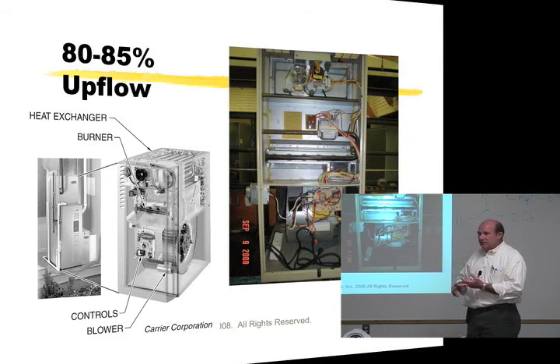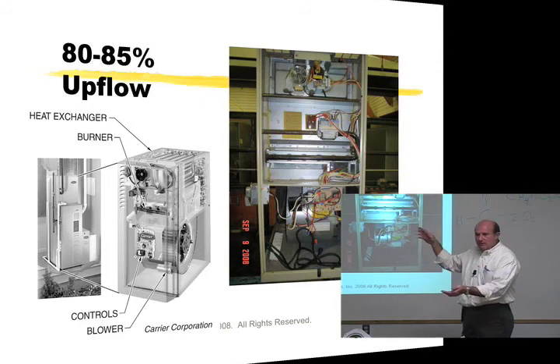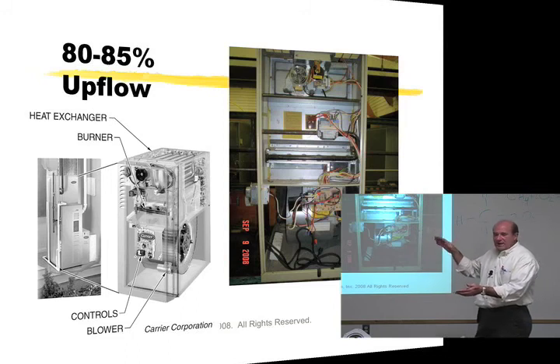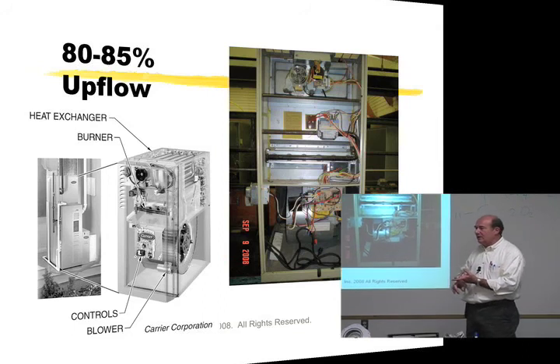And the reason is that when we're heating a space, if the space temperature is typically in the 68 to 72 degree range, the temperature coming out of that furnace might be 120 or 130 degrees. So we've got a 40, 50 degree temperature differential between the actual space temperature and the actual temperature of the air that we're delivering to this space. In cooling mode, we have a much narrower range. If it's 72 or 74 degrees in the space, we may only be getting 55 or 58 degree air out of the furnace. The differential is only 16, 18, 20 degrees. We need more air to pick up a thermal load because the disparity in temperatures is so much closer. So we need more air for cooling than we need for heating.